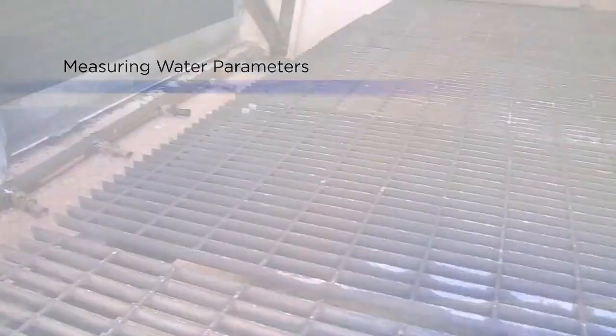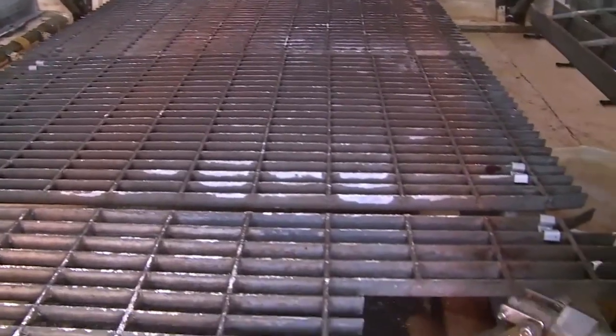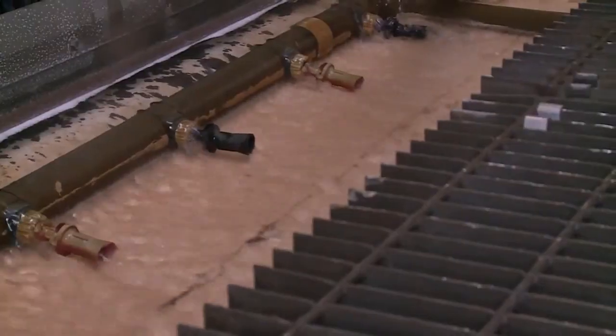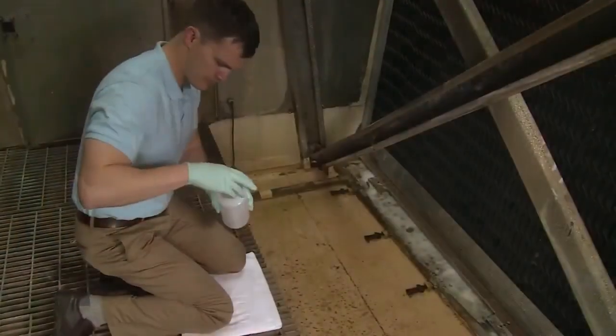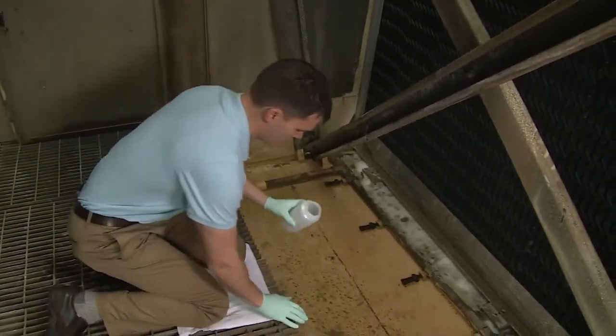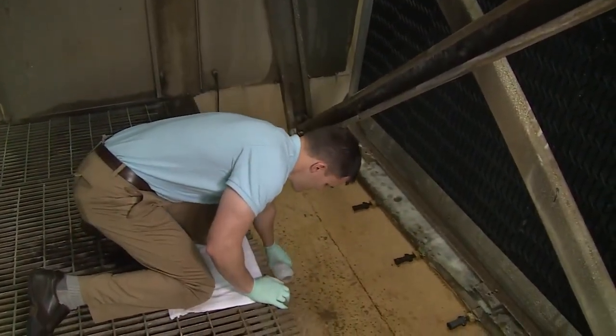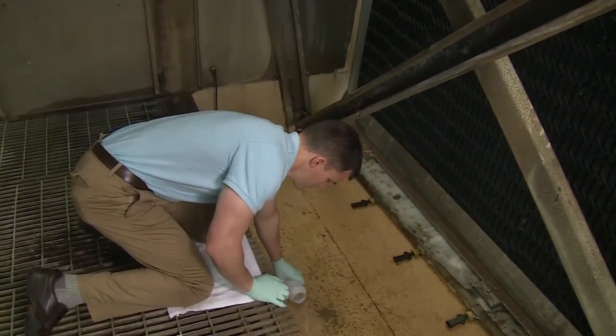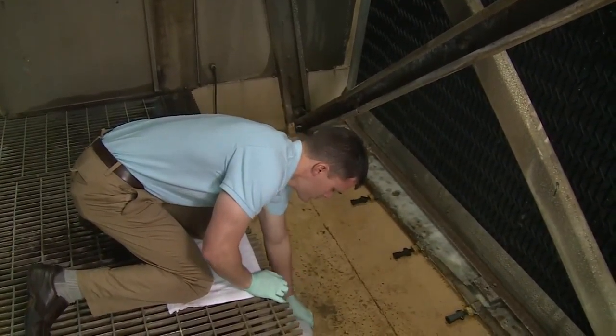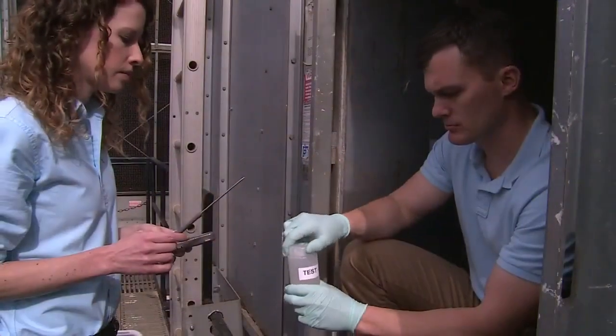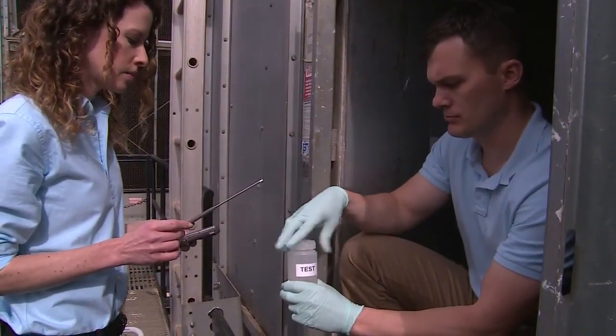You will also need to measure the cooling tower's water parameters. Collect some water from the basin in a separate plastic sampling bottle. If there is not enough water in the basin, you may measure water quality parameters directly in the bulk water sample. But be sure to disinfect probes with an alcohol wipe to prevent cross-contamination of samples.